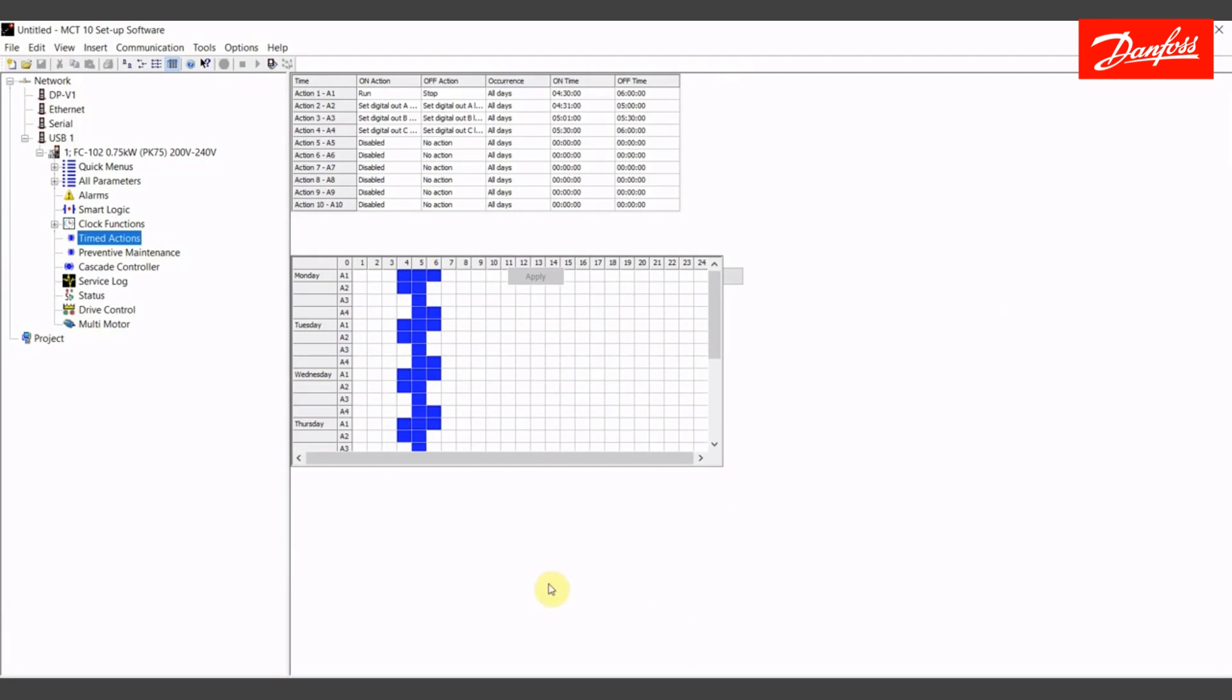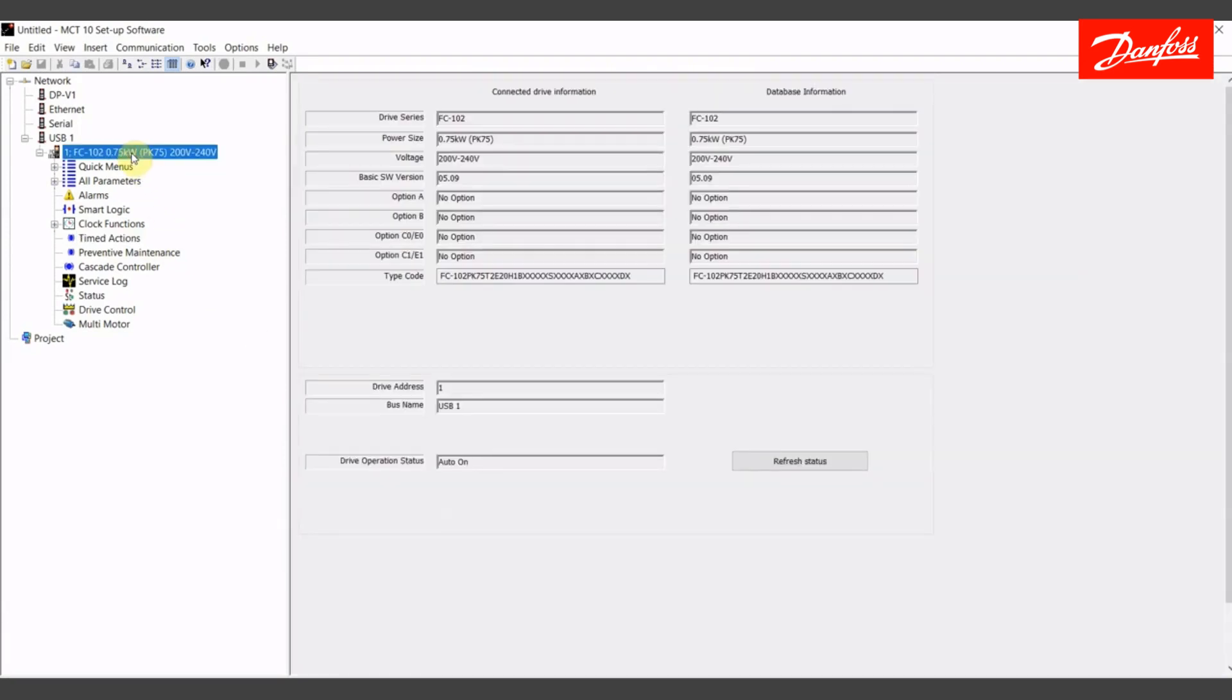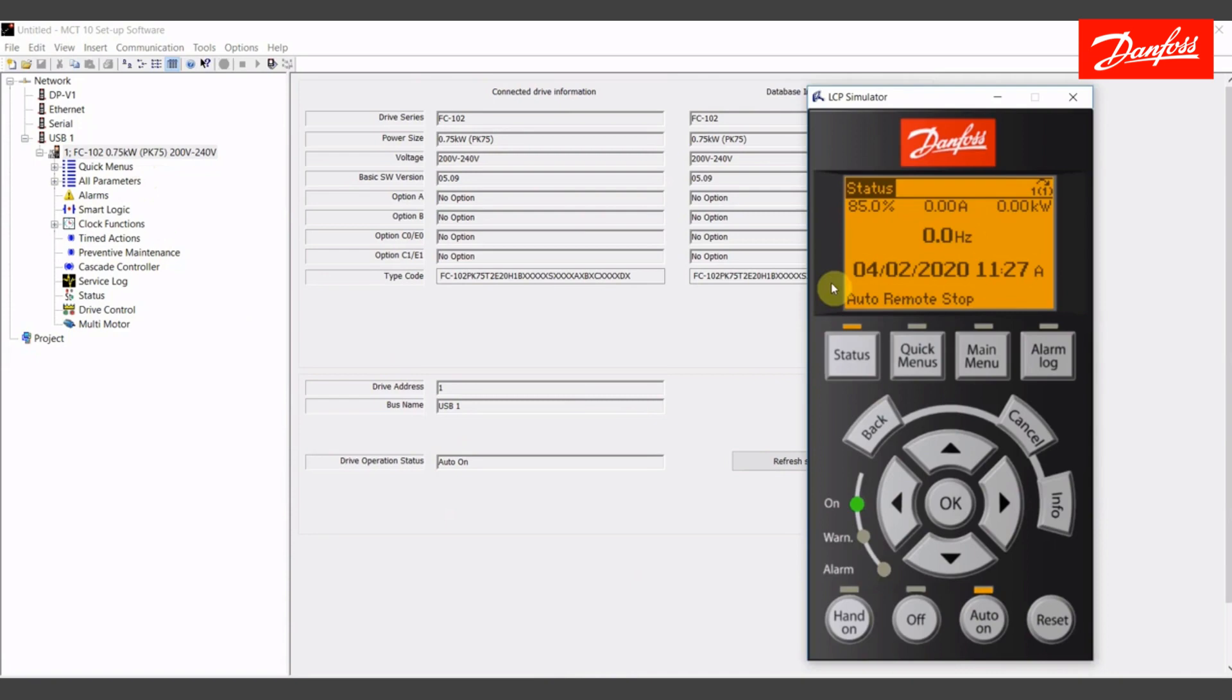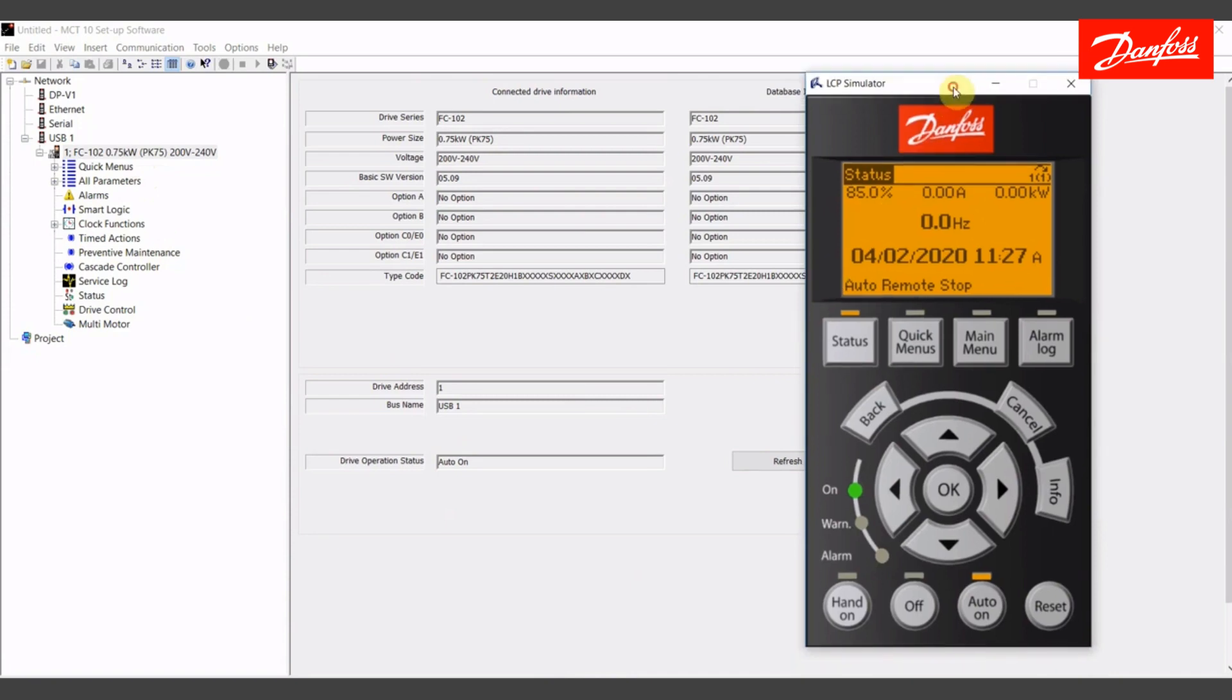I have my MCT-10 software open. I have a connected FC-102 HVAC drive. I also have the live drive sitting here next to me that I am connected to, and this keypad simulator is reflecting that drive right now. This application, we're going to simulate a golf course irrigation application.